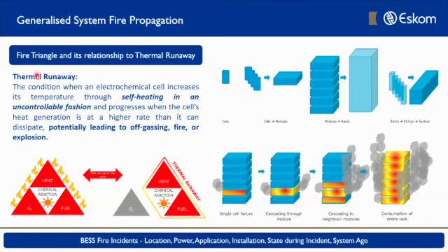The problem with thermal runaway, the term used with batteries, is that once it starts occurring, you actually don't need oxygen. So our normal way of extinguishing a fire, by smothering it and taking away the oxygen, doesn't actually work on a thermal runaway fire.